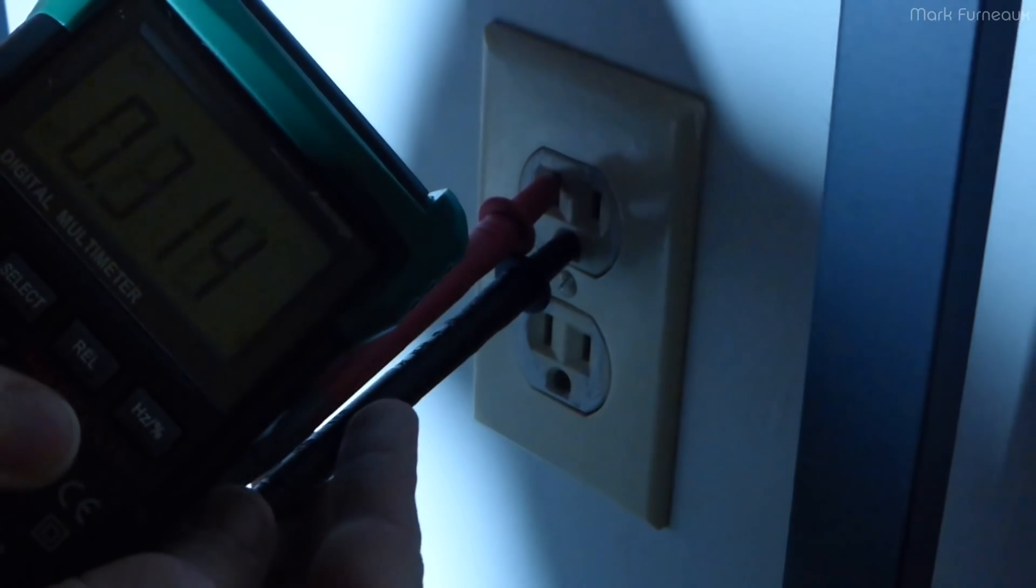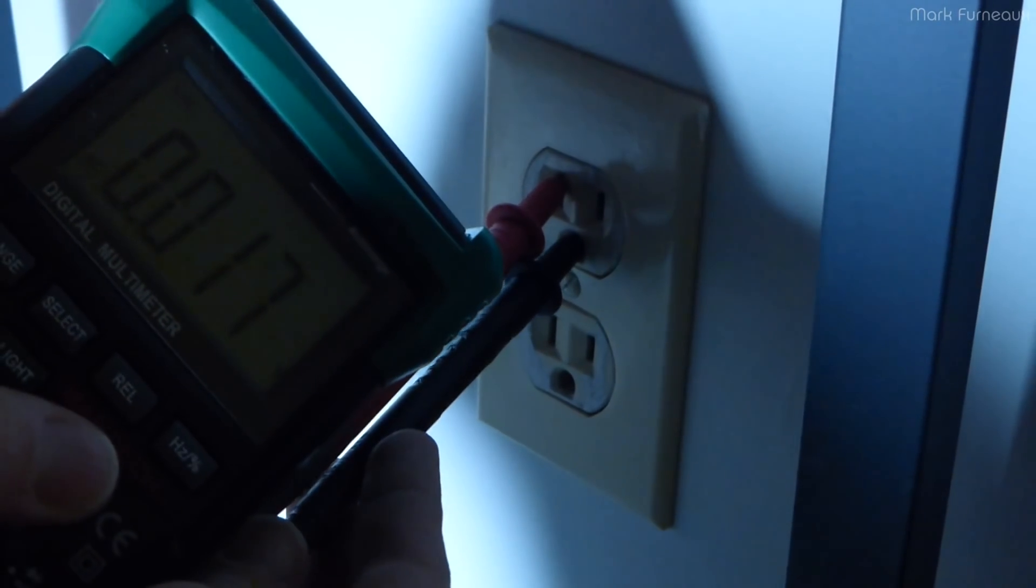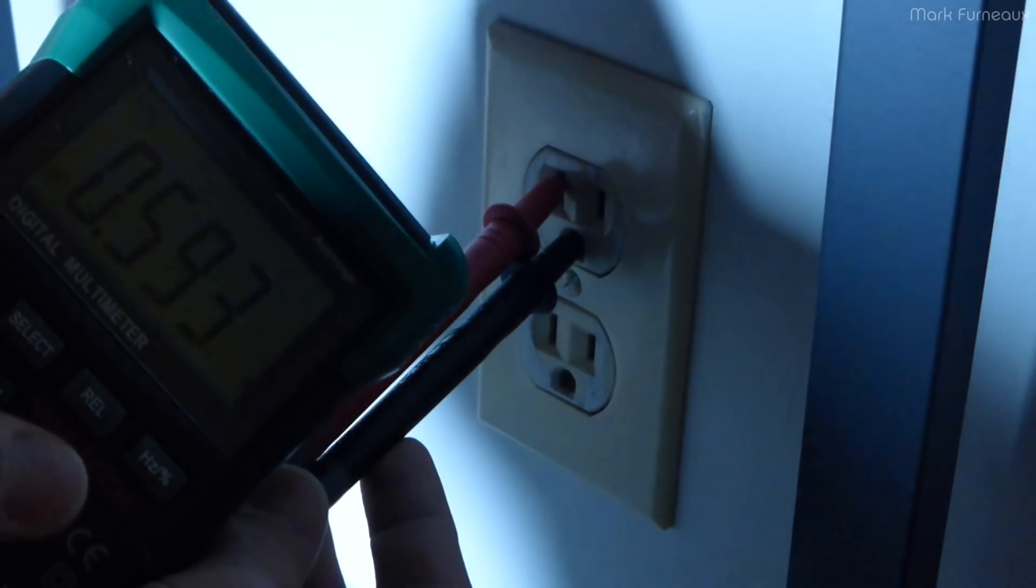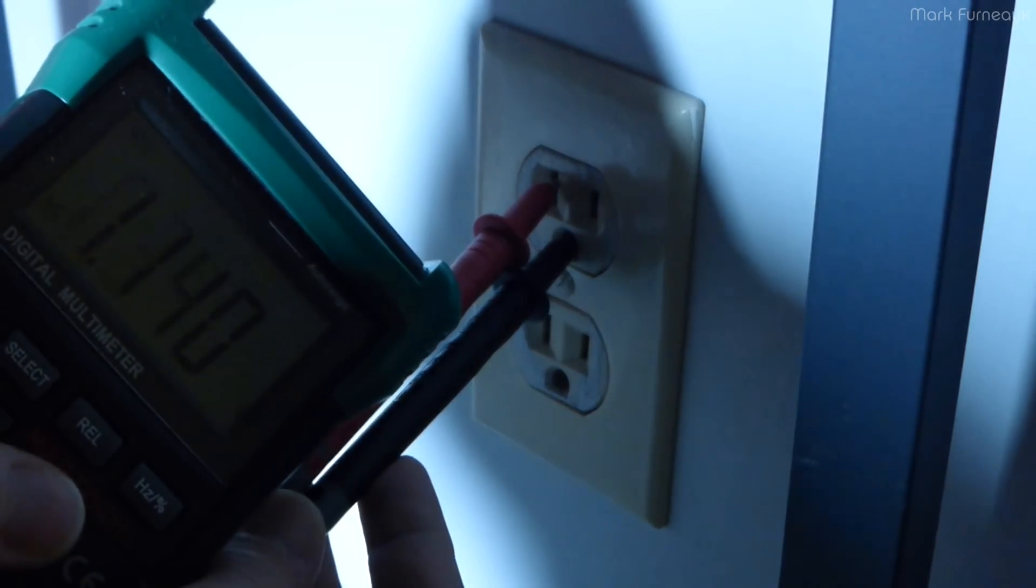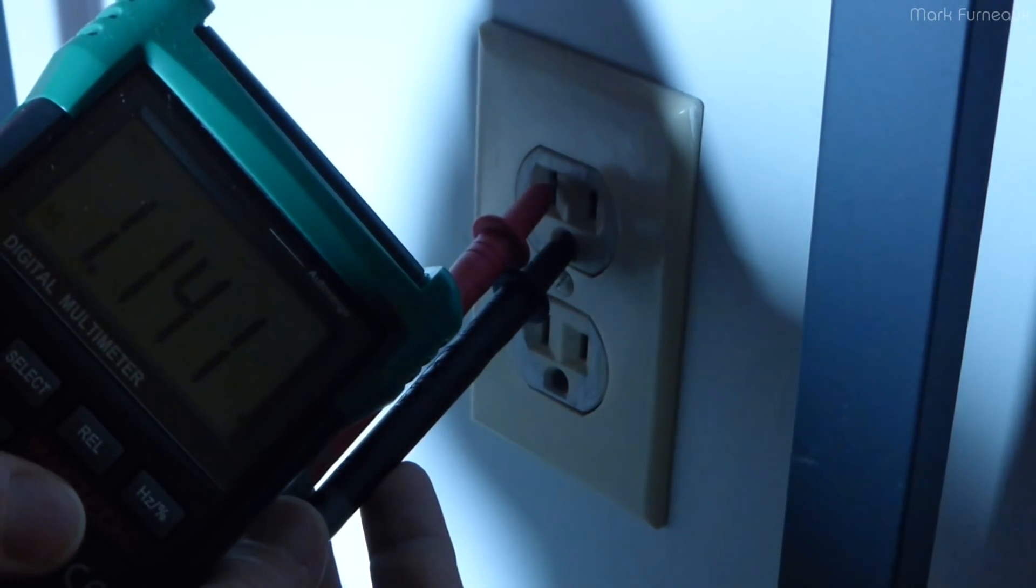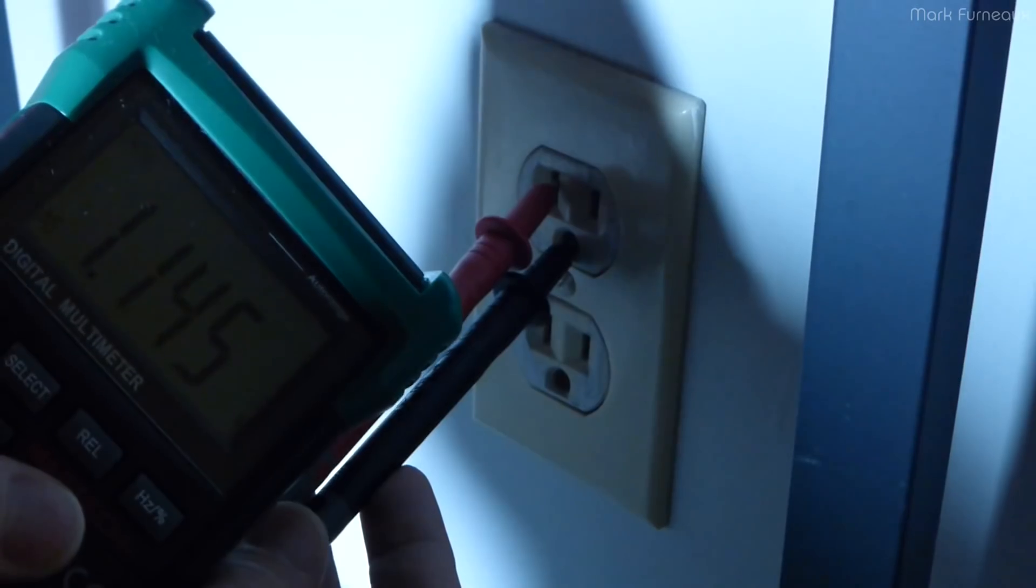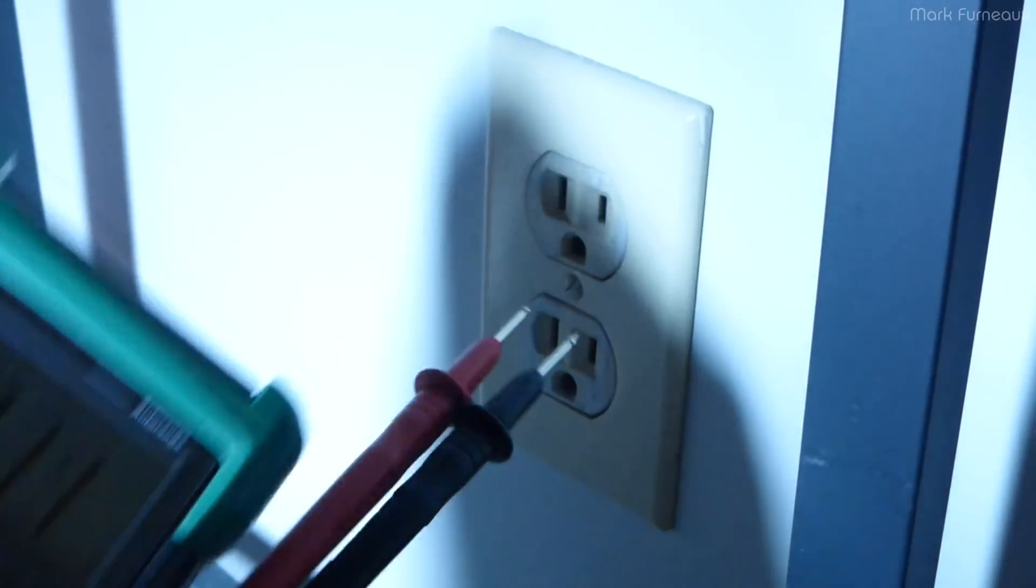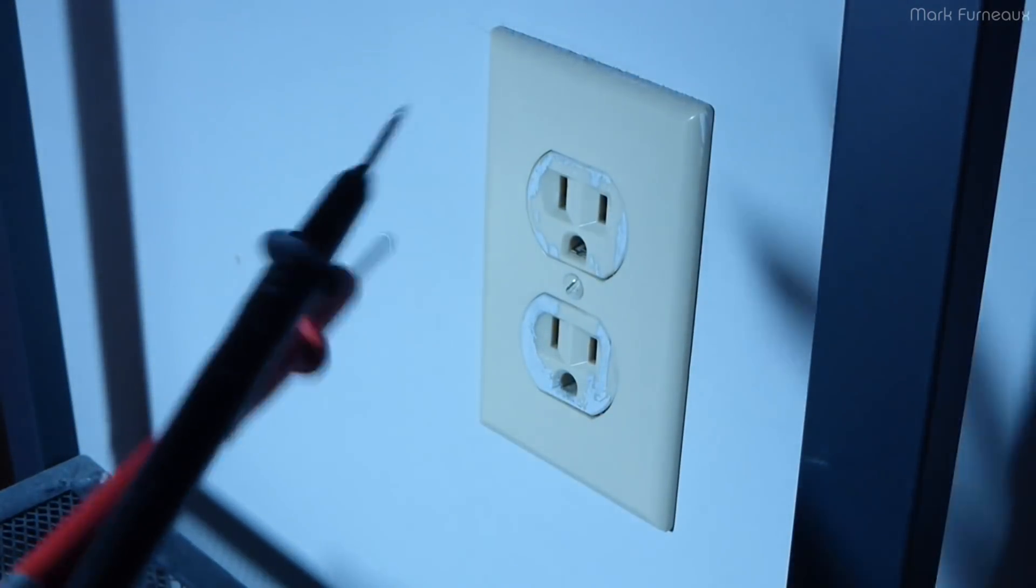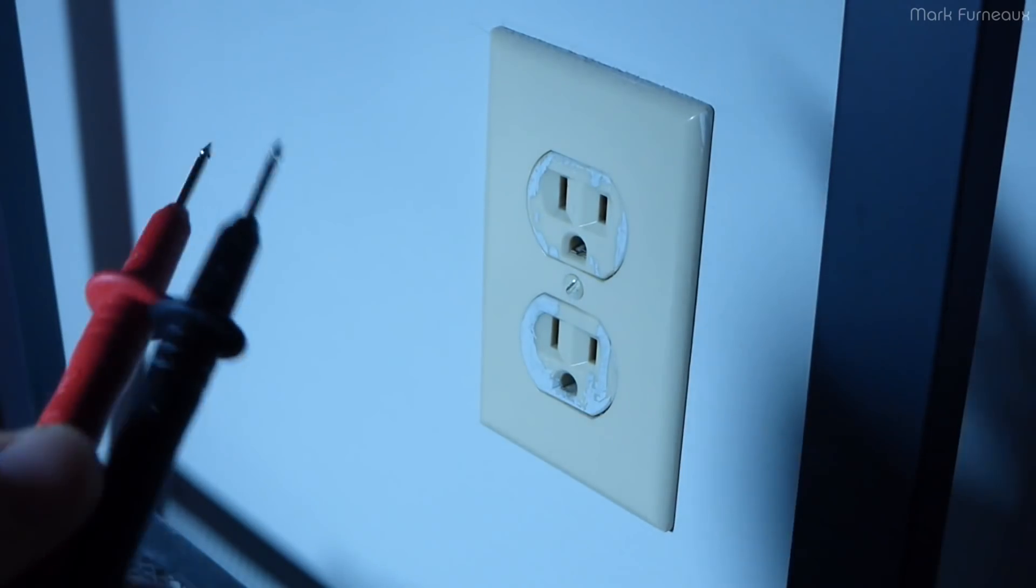And you can see I'm seeing about 1.1 volts or so. It jumps around a bit because the ground connection isn't terribly great. But the highest voltage that I'm seeing is about 1.1 volts or so. So really not that... There we go, 1.1 volts. So if you were to touch the neutral in this instance, you probably wouldn't get a shock.